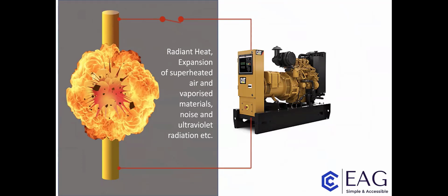Large amounts of current will flow, creating temperatures as high as 20,000 degrees centigrade at the seat of the arc, which will immediately vaporize any element known to man. There'll be a massive expansion of air and vaporized conductor material, which causes an electrical explosion. The thermal effects can cause horrific burns, and ultraviolet radiation can cause arc eye. Ballistic effects can cause blunt force trauma to anybody standing close by.